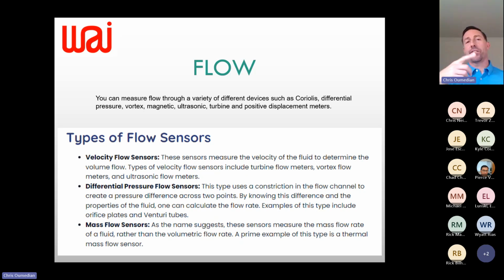Within mass flow sensors, you'll see a lot of paddle wheel - literally like the old water wheels from the 1700s-1800s that generated power. It's a paddle wheel that spins with a counter; as the liquid goes by, it counts how much passes, and based on the diameter of the pipe you equate the ticks to a flow rate. It's a fairly accurate, very low cost device, requiring a high-speed counter to pick it up. You'll see a lot of paddle wheels.